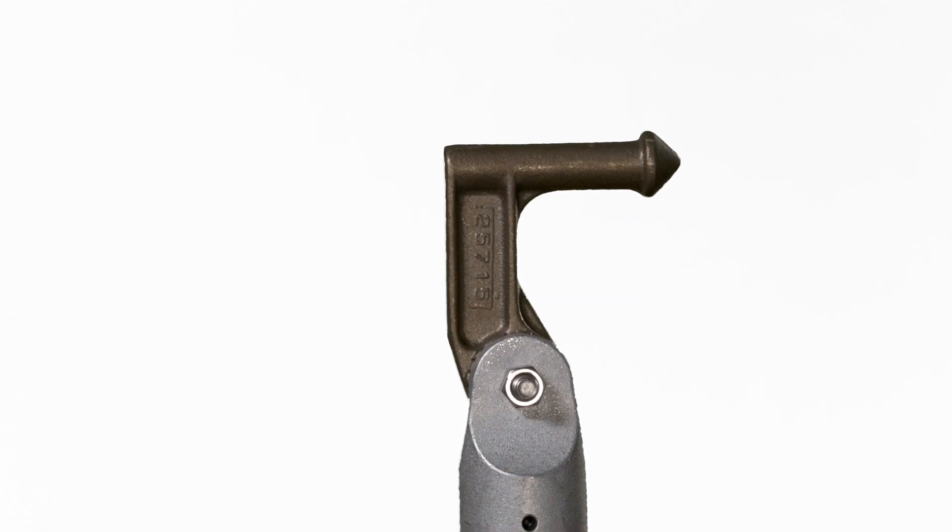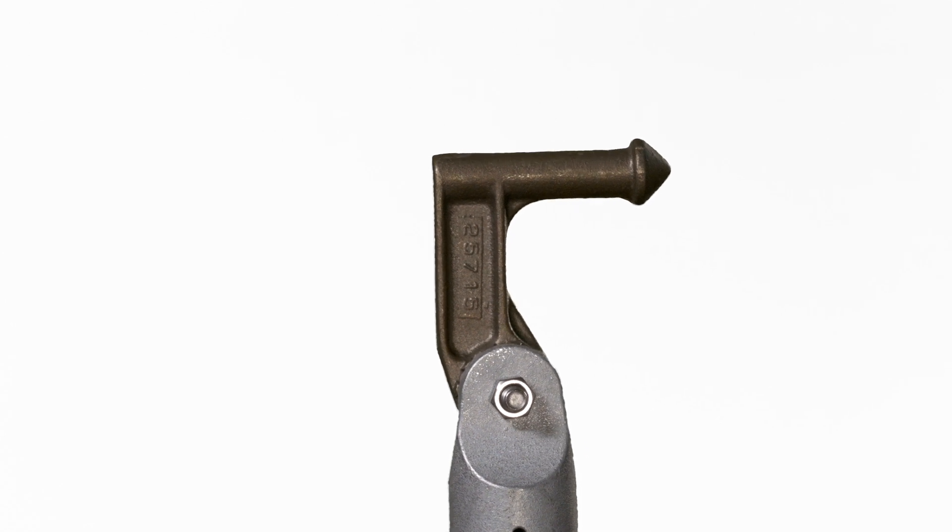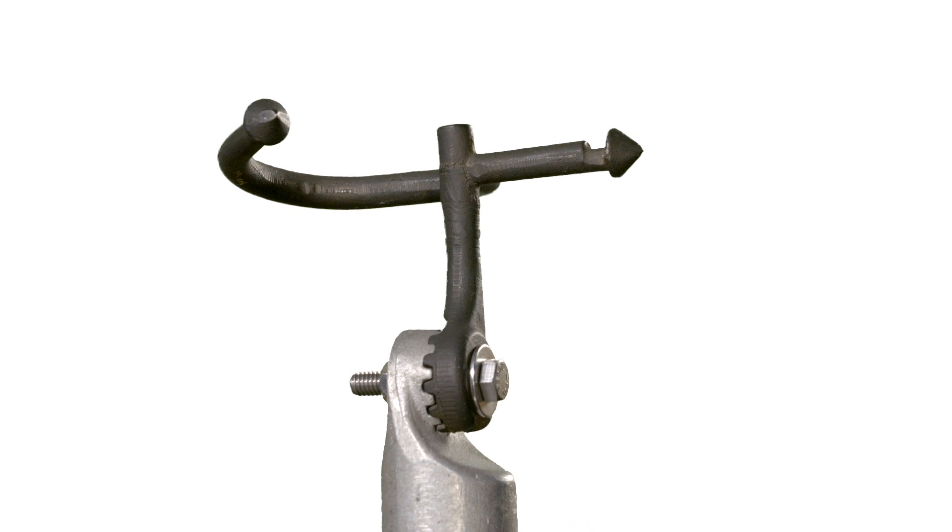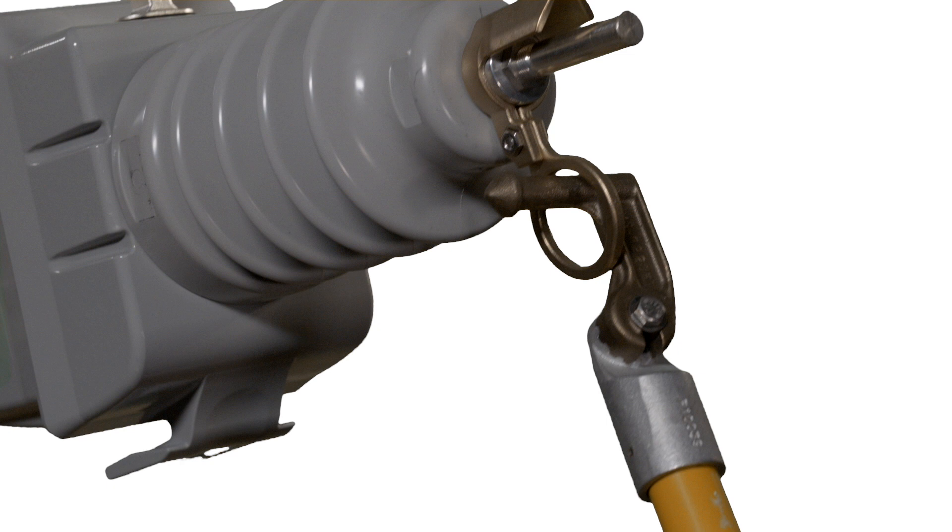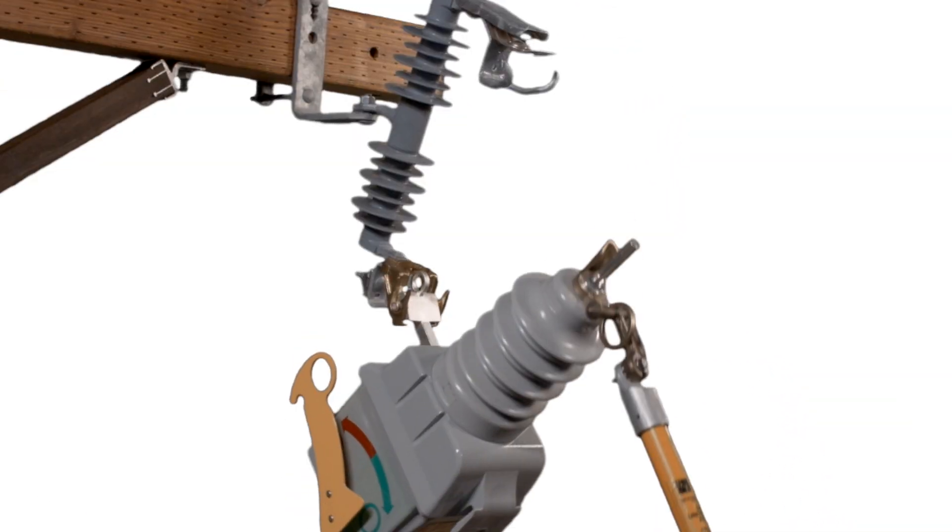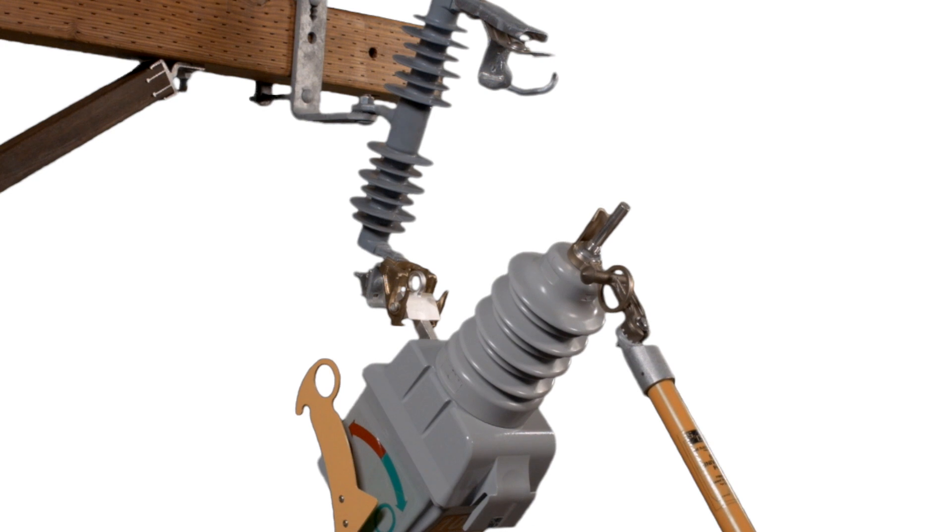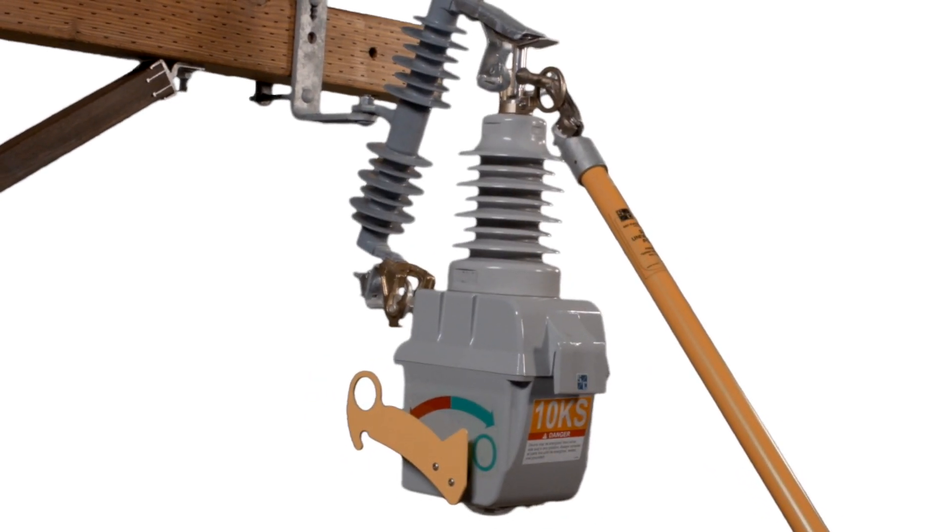Close the VacuFuse Interrupter into its cut-out mounting using a hook stick fitted with a distribution prong or using the straight prong of the S&C Talon Handling Tool. Insert the tool into the pull ring and swing the VacuFuse Interrupter to within approximately 45 degrees of the fully closed position. With a firm grip on the hook stick, drive the VacuFuse Interrupter closed with forward force. Maintain this force until the VacuFuse Interrupter properly closes and latches into the cut-out mounting.